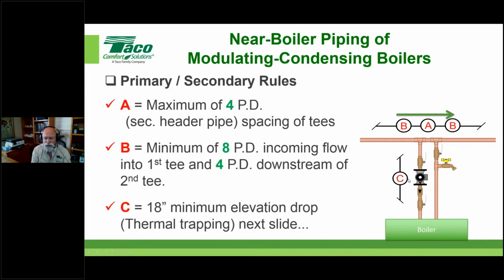The C note here is just actually having hotter water higher than the cooler water, so you get some thermal trapping going on. And again, that's kind of a throwback to the variable speed injection mixing. We're not going to spend any time on the C note, but just try to remember that the hotter water needs to stay higher than the cooler water in mixing primary secondary.